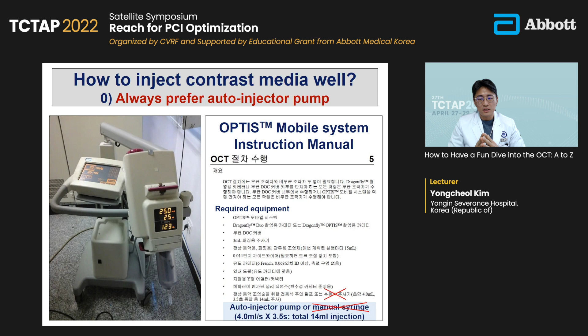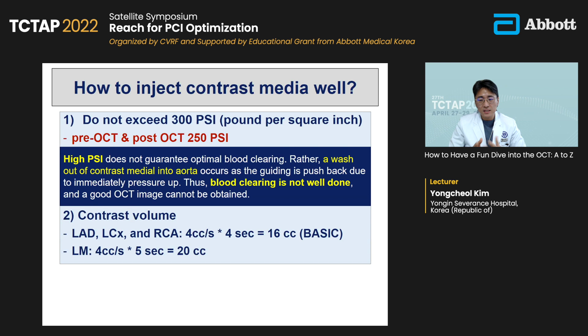There is no doubt that an auto-injector pump should be considered if you are not a master of OCT. When you set up the auto-injector, do not exceed 300 PSI, because a high PSI leads to washout of the contrast media into the aorta due to the immediate pressure rise. So we set 250 PSI for pre- and post-stenting PCI in our center. Regarding the contrast volume, the total amount is 16 cc during 4 seconds.